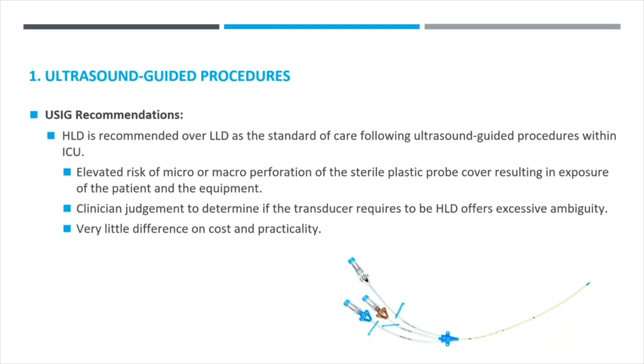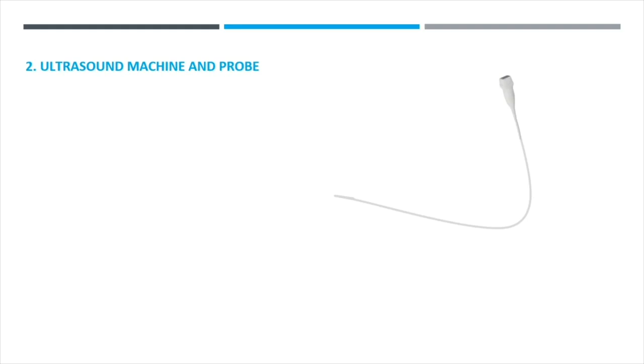Next thing I'd like to talk about is the probe and the machine. The 2017 guidelines really specifically refer to probe-only reprocessing or disinfection, and this is because they are reusable medical devices. The rest of the machine is not a reusable medical device and really falls outside the Spalding criteria. But from an infection point of view, this makes absolutely no sense. It's self-evident that the machine can act as a surface for pathogen transmission, and it needs to be disinfected.